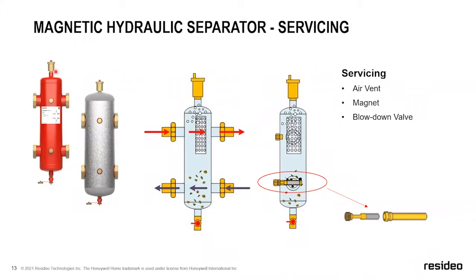And the reason is most engineers will draw out any type of major air elimination with some form of a shutoff valve because they've been doing it for long enough to know that these air vents do fail over time. So they usually want to see a shutoff valve here. I've got an image of that later in the presentation. And then we have a blowdown down here on the bottom.